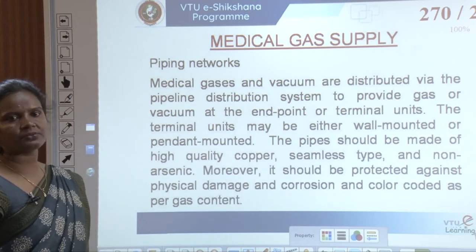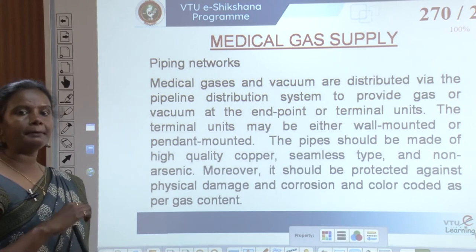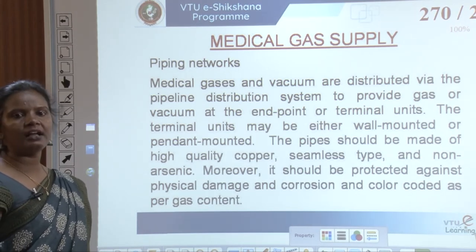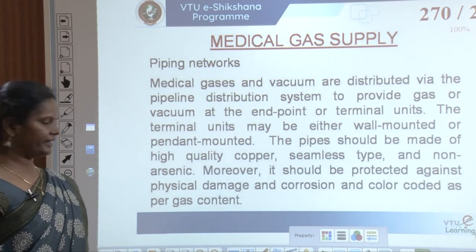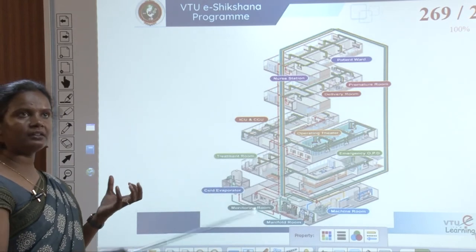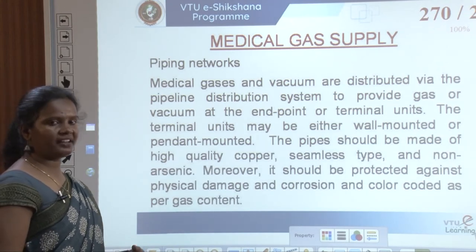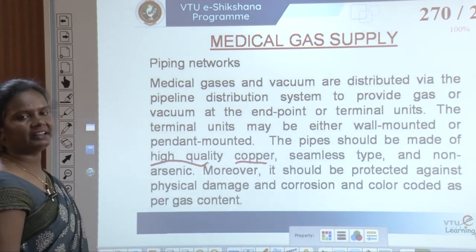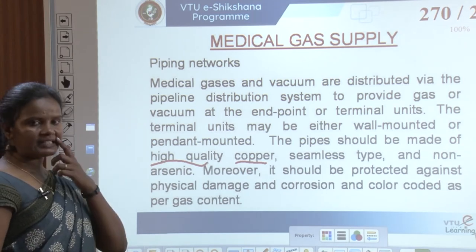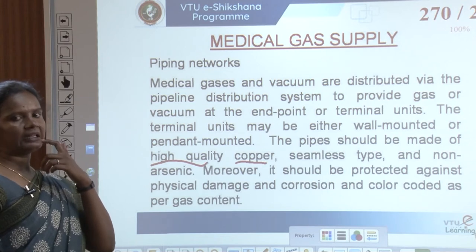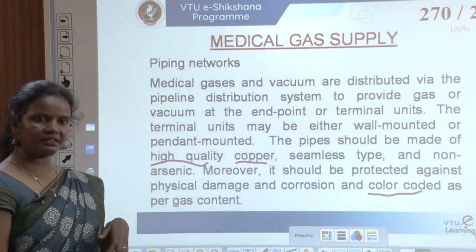Medical gases and vacuum are distributed via pipeline systems to terminal units. Terminal units may be wall-mounted or pendant-mounted (hung from the ceiling or inside the false ceiling). Pipes must be made of high-quality seamless, non-arsenic copper, protected against physical damage and corrosion, and color-coded as per gas content.